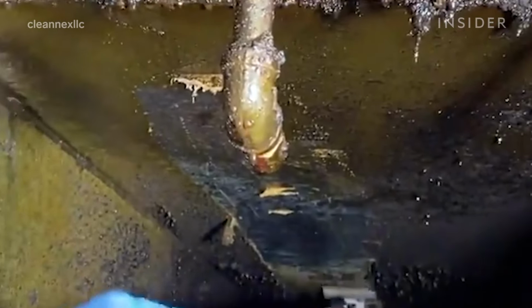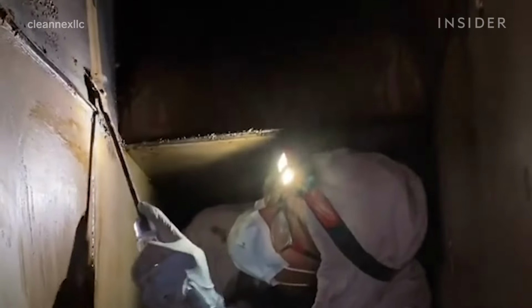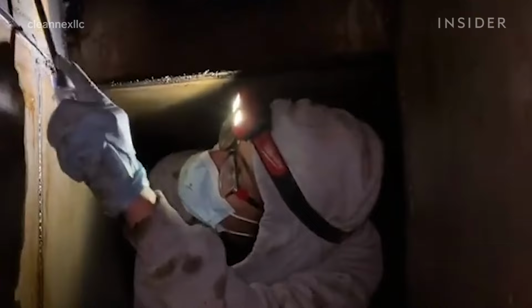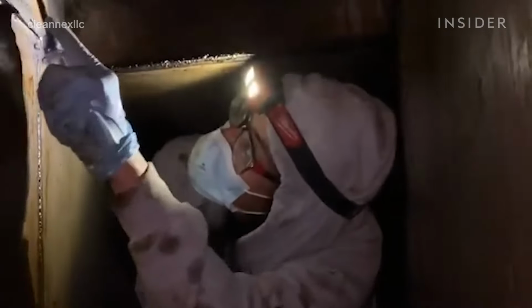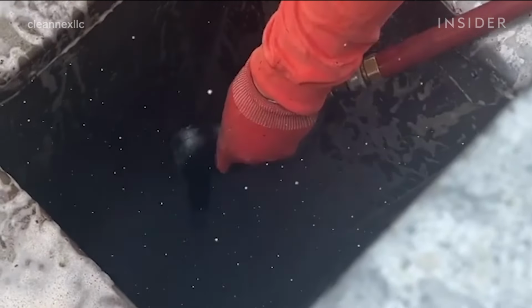It'll go from the yellow color all the way into the black. When it's in the black level, that's an extreme level. That means that the system has not been properly maintained. In these types of designs, we'll use duct spinners and duct brushes. The duct spinner is designed to self-rotate within a protective cage and spray water at high speed, which dislodge buildup from the metal duct.